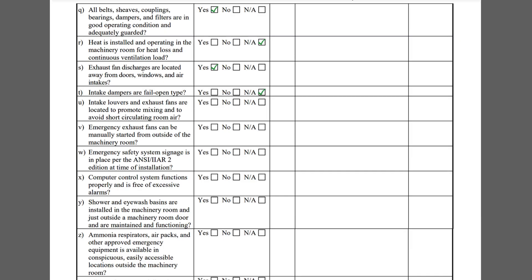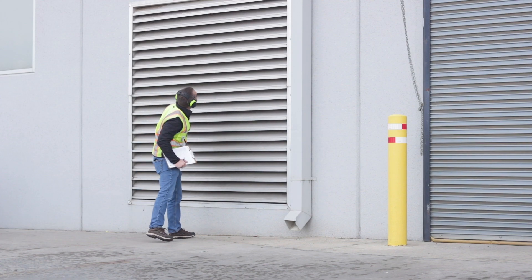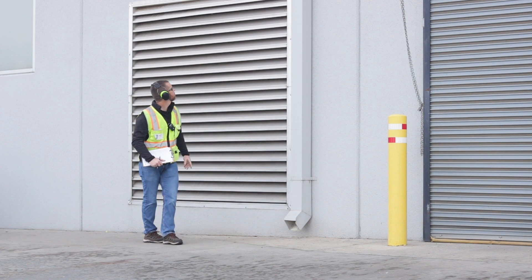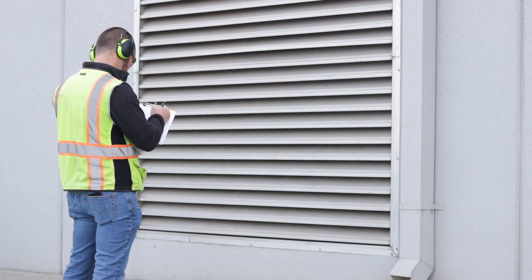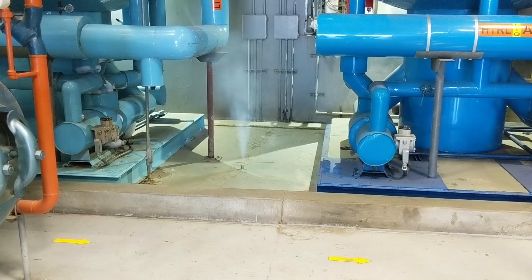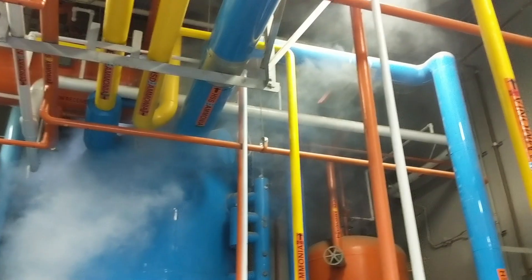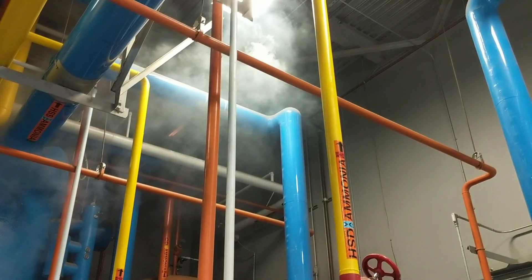Item T and U both pertain to the intake louvers. Item T asks if the intake dampers are fail-open type. Item U asks if the intake louvers and exhaust fans are located to promote mixing and to avoid short-circulating room air. The facility opted to do a ventilation smoke test to confirm the ventilation system was functioning well.